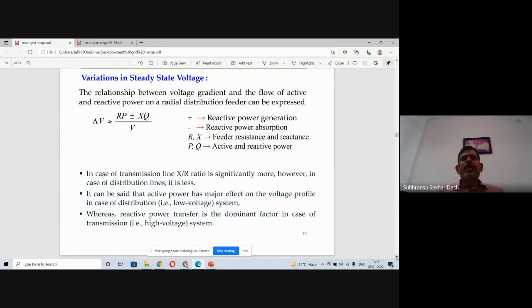In the case of transmission lines, the X by R ratio is significantly more, whereas in distribution lines it is very less. Because if you talk about long transmission lines, X is much more than R. In short lines, X is a little bit less. So it can be said that active power has a major effect on voltage profile in distribution systems, whereas reactive power transfer is a dominant factor in transmission systems.